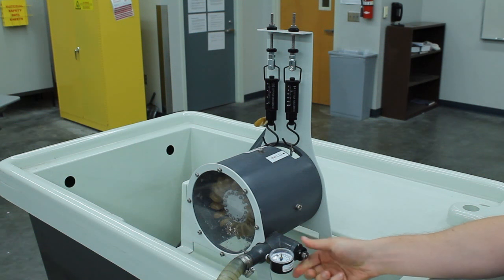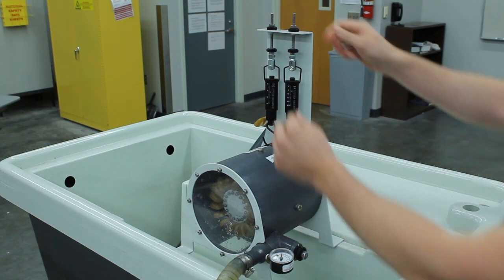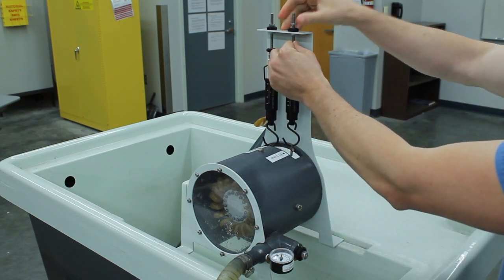Release the pressure in the feed line by briefly opening the spear valve. Adjust the screws at the top of the spring balances to release the tension.